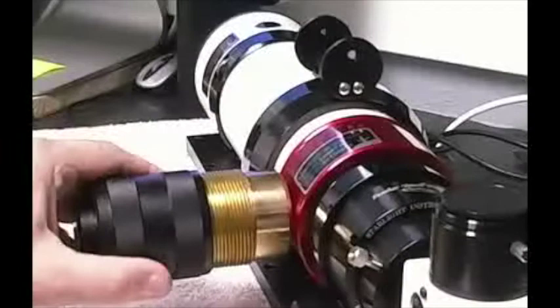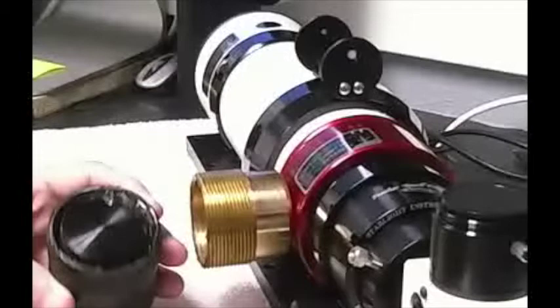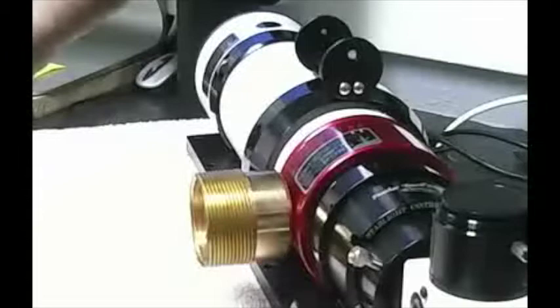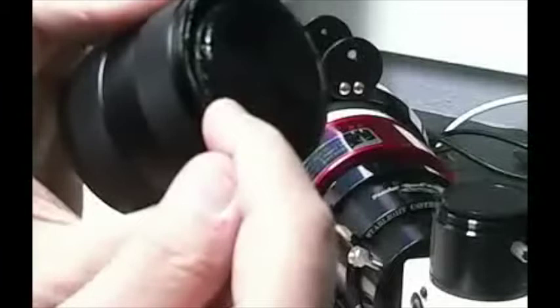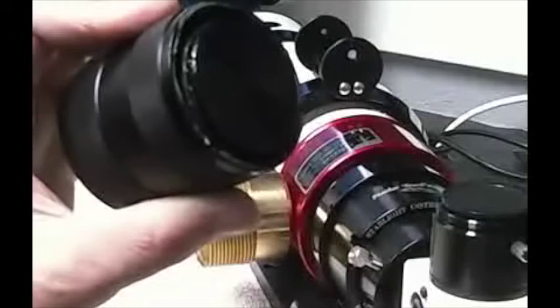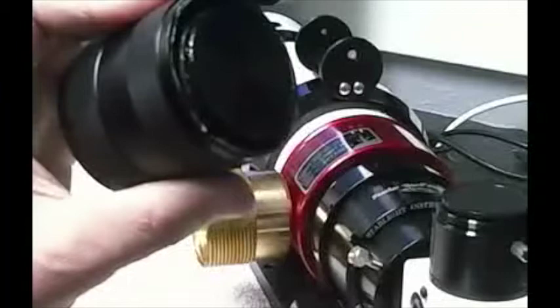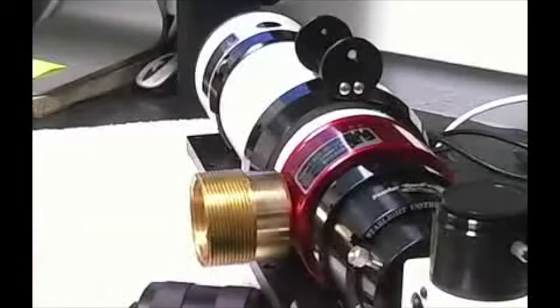We're going to back this out — there's a seal underneath here which I've never had off, so bear with me. I think I can see the seal on the end. There's a rubber seal right on the end of this cup right here. Craig is telling me to check for pitting on that rubber o-ring — scarring, cracks, breakage — and just see what kind of general shape it's in. I'm going to set this down, wipe my hands of the grease, and I'll be right back.